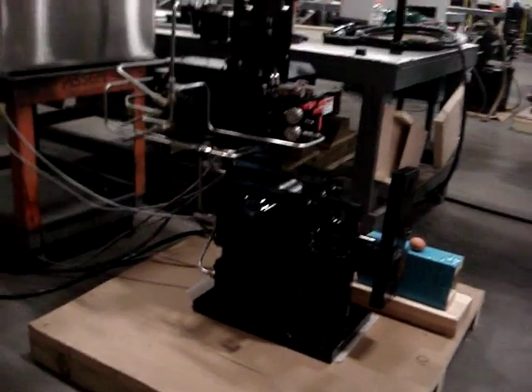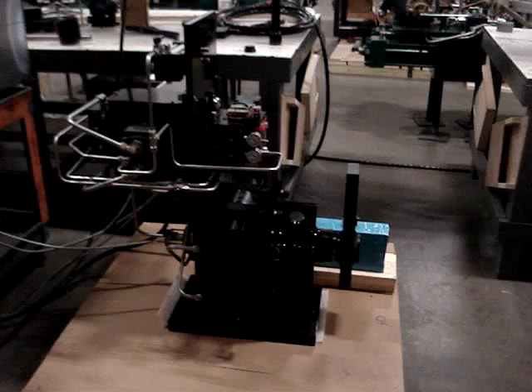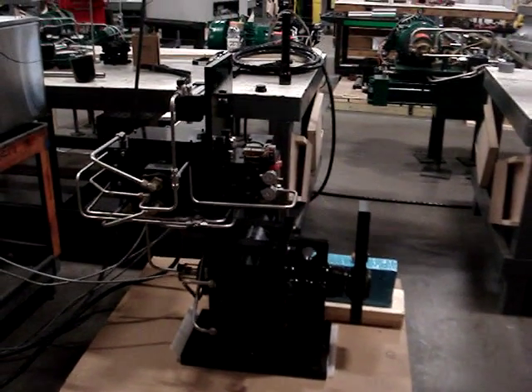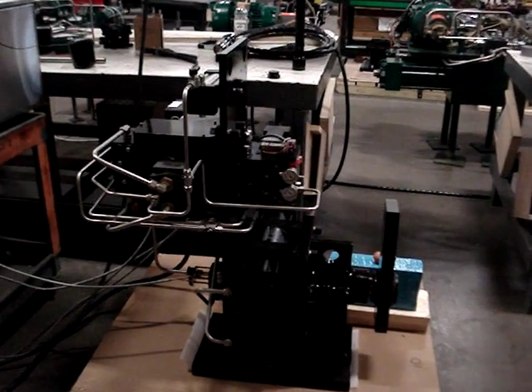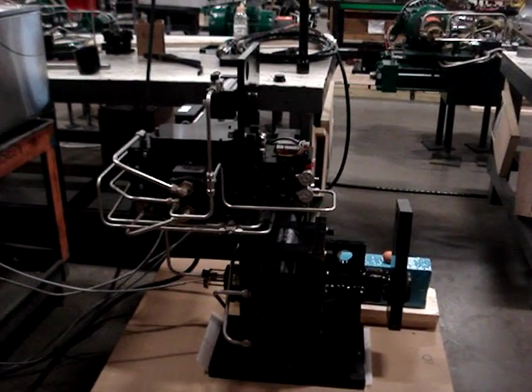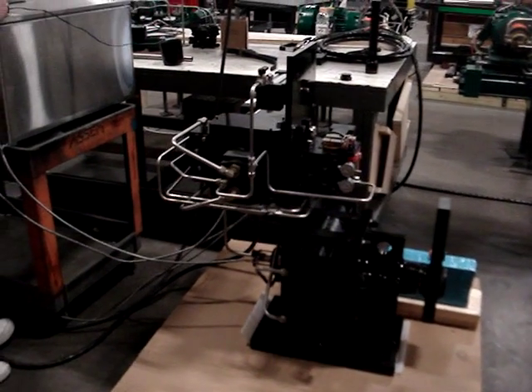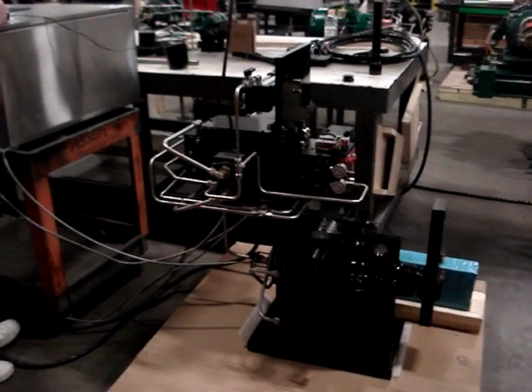This is a closed-loop electro-hydraulic actuator. There's no separate oil tank, no reservoir, no filtration. It's basically a motor-driven device. So when we change the control signal — it's a 4 to 20 milliamp input — the motor activates and the drive moves.